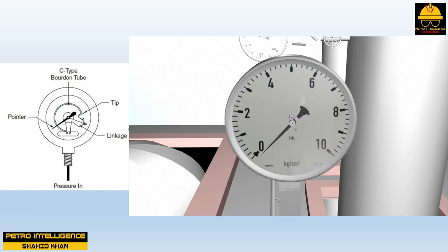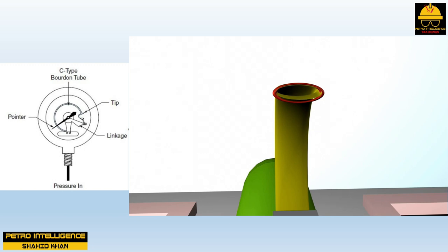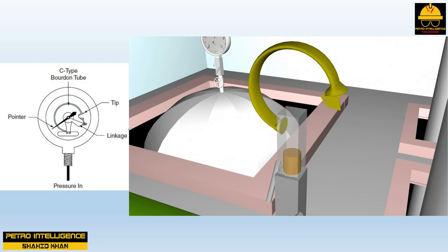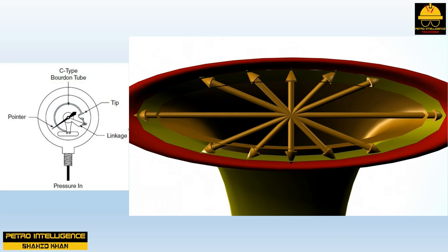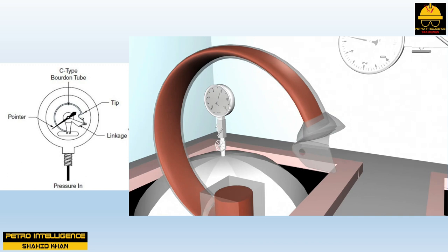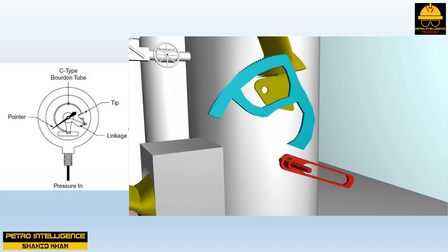The most common type of pressure element is a Bourdon tube. Bourdon tubes come in a variety of shapes: C-type, helical type, and spiral type. C-type Bourdon tubes are named for their C-shaped hollow pressure element; they are composed of a C-shaped hollow tube, a pressure inlet, a mechanical linkage, and a pointer. During operation, the tube expands and contracts in response to pressure changes — sometimes called elastic deformation — moving the mechanical linkage and pointer. Bourdon tubes measure a wide variety of pressures including vacuum; helical and spiral types operate the same way.